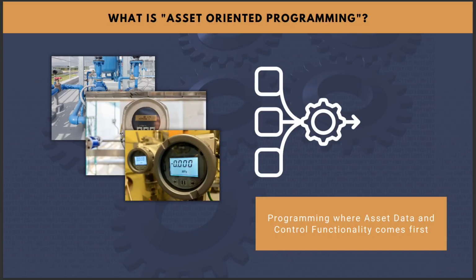Essentially, the bare bones of asset-oriented programming is that each asset has its own data set and associated management system. That's a function block that uses a UDT basically to not only hold the asset's information in one place, but to standardize the data and then use a standard function block with that standard data to ensure that every single asset operates exactly the same way and is ready to be packaged up into a library.